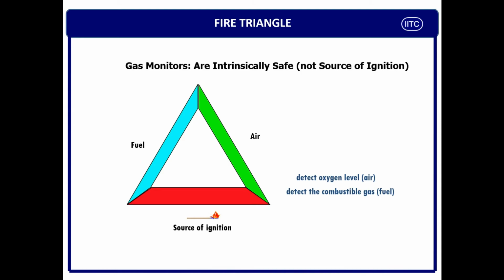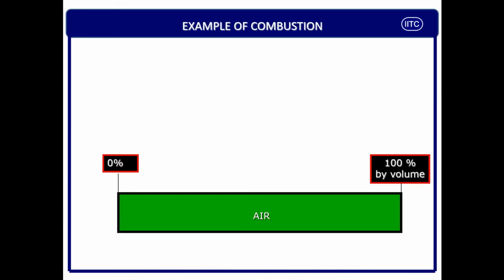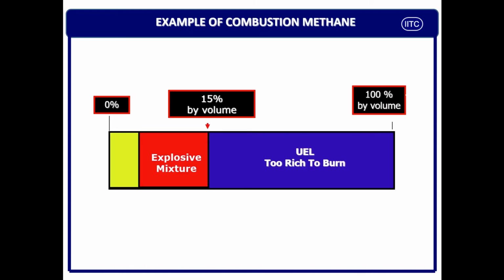Gas monitors are absolutely intrinsically safe. So a source of ignition is never possible from the gas monitor side. Now we will understand what is the LEL, what is the UEL, and what is the explosive mixture. This is the scale of 0 to 100% of the air. Here we are going to share the example of methane gas. The yellow legend is not flammable, not explosive, because it is too lean to burn. Probably there is methane gas, but not enough that it can ignite. The moment the yellow legend ends, you get red.